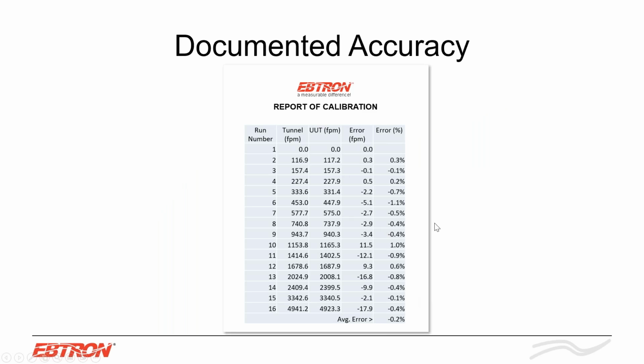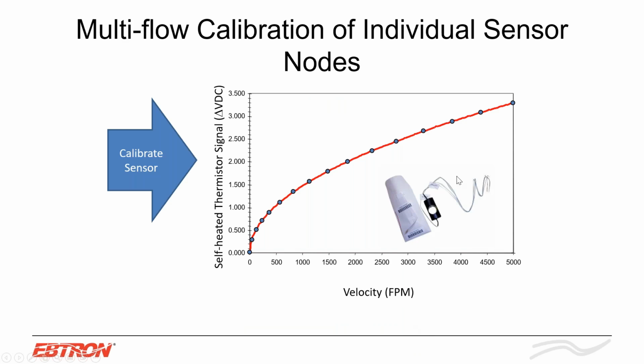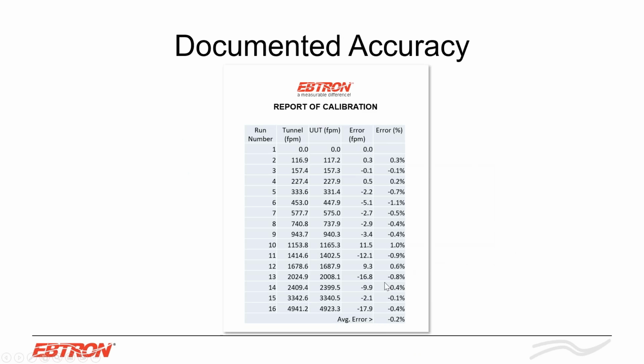This is just an example of a reported calibration from our production line. And as you see, there's a 0.2% error for this sensor node right here. Now we are very conservative in what we say, and we say plus or minus 2% of reading for each sensor node. But a lot of times they're under 1%.